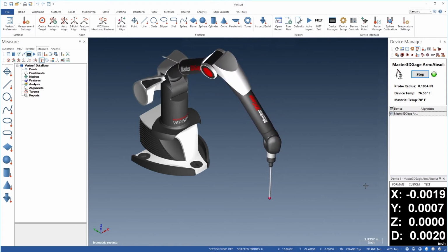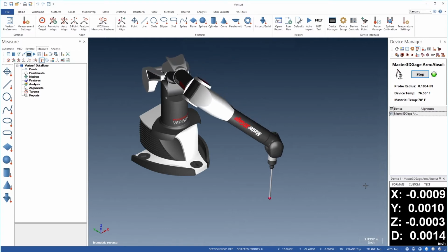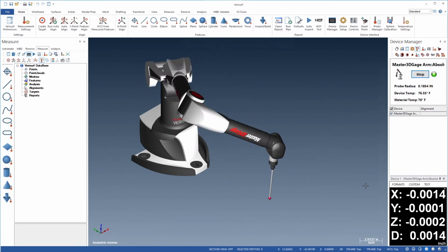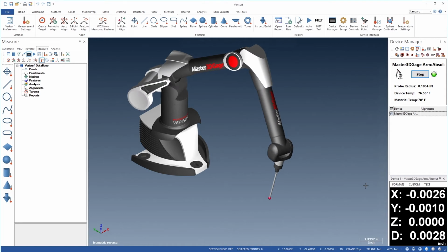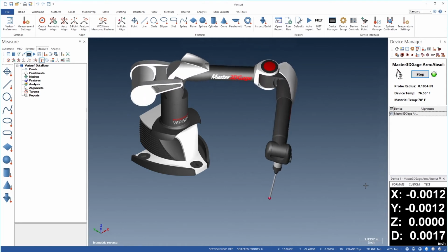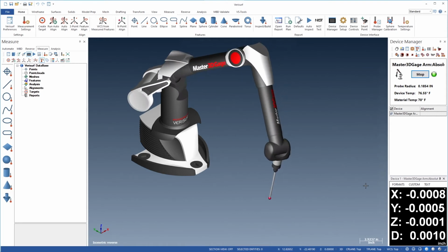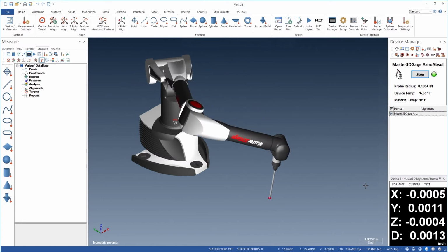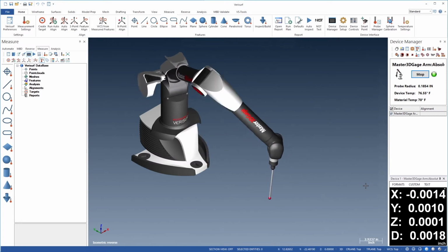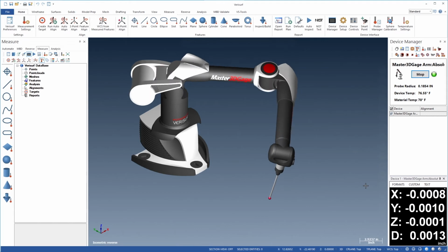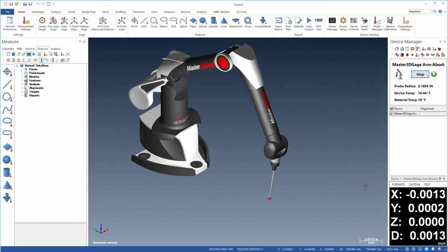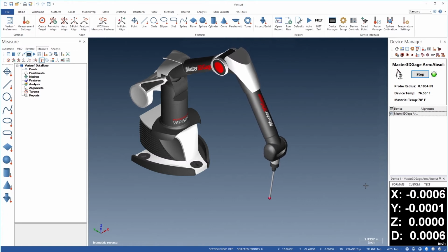the measurement task. As an additional test, we'll evaluate the stability of the probe location by flipping the arm's elbow from side to side, holding the probe shaft vertical. This test should yield the same results as the previous one. If either test shows large deviations following calibration, it could be due to device or nest movement or flexure of the probe shaft.